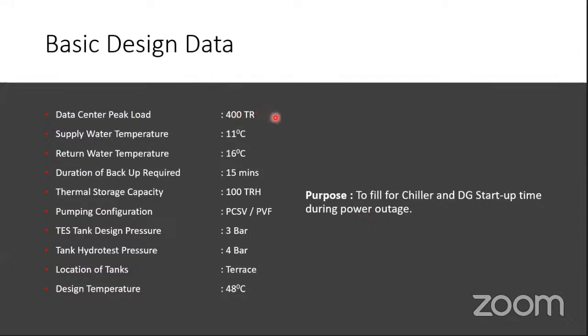So let us say that the peak load of the data center is something like 400 tons, and the supply water temperature is 11 and return water is 16, and nearly 15 minutes of backup is being planned for. TRH is our thermal energy storage capacity. We convert 15 minutes into hours, 15 divided by 60. So when we calculate TRH using the tons and hours, that's what we get, 100 ton hours.